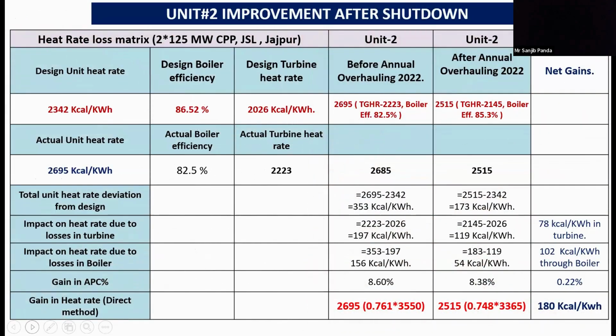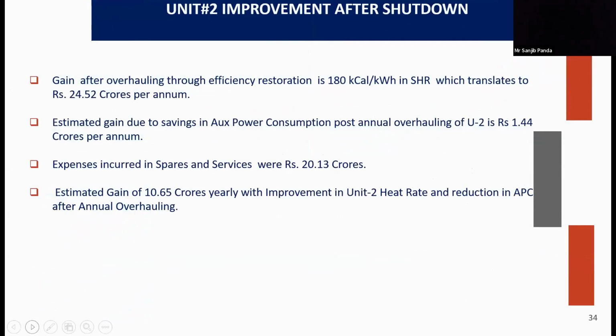Similarly, for Unit 2, as I said, both are 2 different units. In that, we have seen there was improvement of 148 kilocal per kilowatt hour in heat rate, and here in Unit 2 we have gained 180 kilocalorie per kilowatt hour, which means that there was more potential in improvement in Unit 2 than Unit 1. And we can also interpret it this way that based on our experience in Unit 1, we could still better our implementation in Unit 2. Yes, ma'am, next. This is again what is the calculation for the Unit 2. So we can go next.